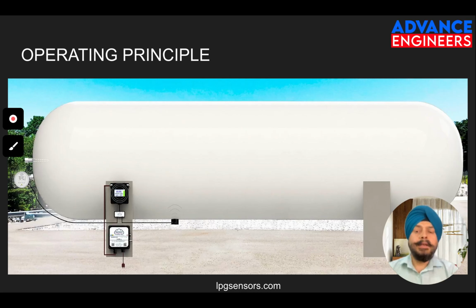Now your question will be, the density of LPG is going to change with temperature, which is a valid question. Here the accuracy is maintained by the same principle. The sensor, when bonded to the bottom of the vessel, also measures the temperature, not the surface temperature. Although it's measuring the temperature, it has an inbuilt algorithm. When you feed in the MOC of the tank, the thickness of the tank, and the media inside the tank, it automatically calculates how much the temperature inside the vessel is, and compensates for that to give you an output where you are able to measure a proper level of LPG.